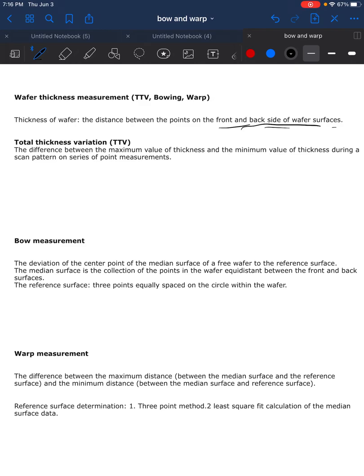In reality, in each measurement we need to have a calibration first of the system. Let's say this is a wafer and we have probe A and probe B. In order to calibrate this, we need to use this system to measure a wafer of known thickness.